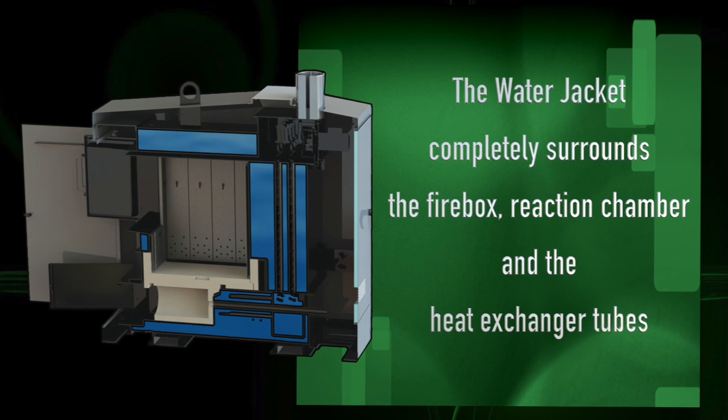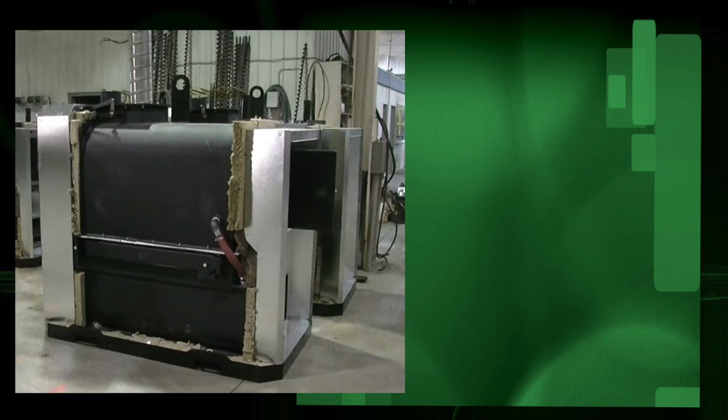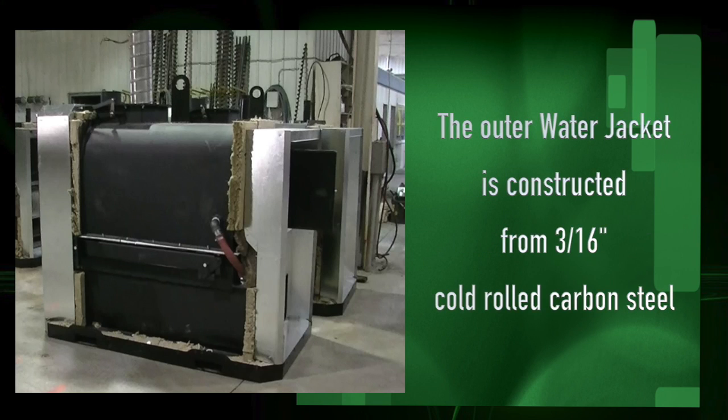The water jacket completely surrounds the fire box, reaction chamber and heat exchanger tubes. The inner wall of the water jacket and fire chamber are constructed of quarter inch cold rolled carbon steel and the outer water jacket is 3/16th cold rolled carbon steel.